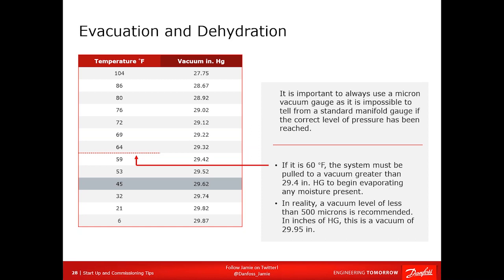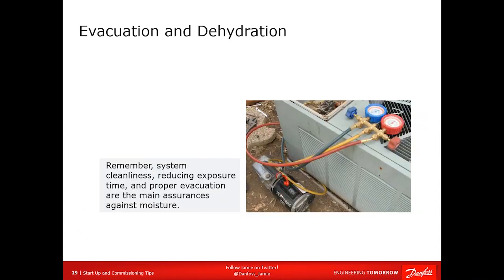Number 2, pull down to the recommended 500 microns. If you can't pull down, there is a reason. Either you have a ton of moisture or a leak. If you stop the vacuum pump and the pressure rises and plateaus, that means you have moisture, and the water was boiling until the pressure rose above its saturation point. If the pressure keeps on rising, well, you have a leak, and hopefully it's not somewhere in the condenser, but that leak needs to be fixed, all right, somehow. So all these tools allow you to effectively evacuate, make sure you have the proper vacuum, and save yourself a ton of time, all right? So always recommend bleeding nitrogen through the system before you put the torch on it and before you unplug the compressor.